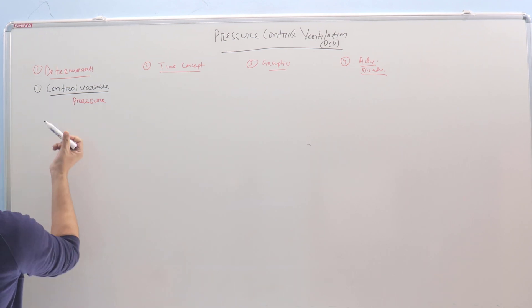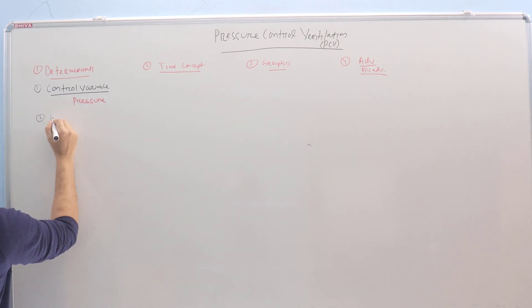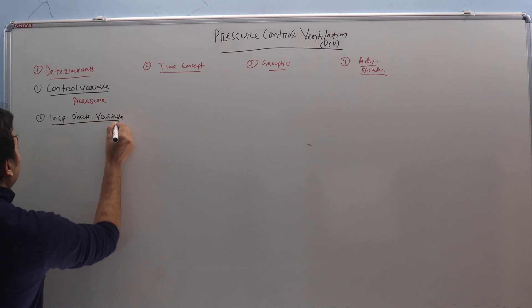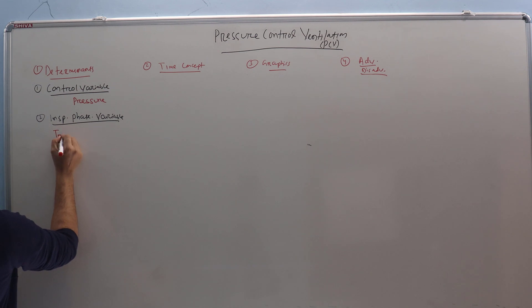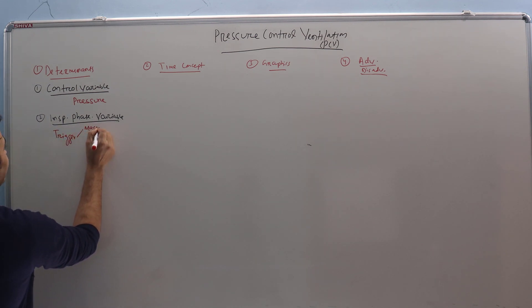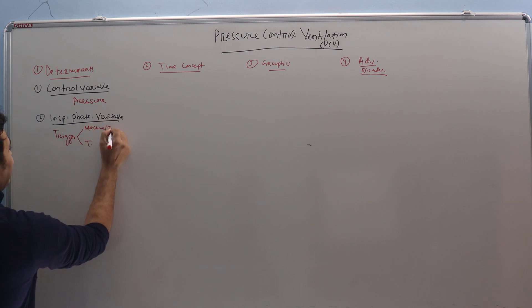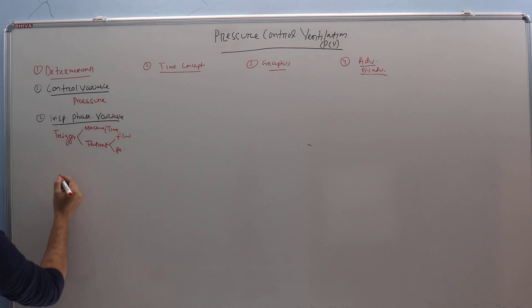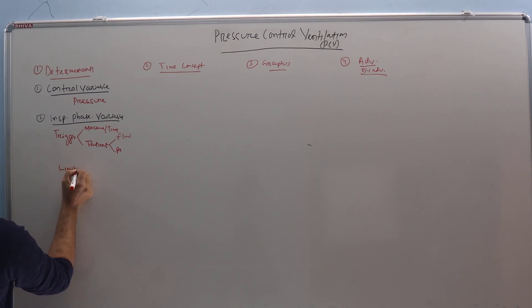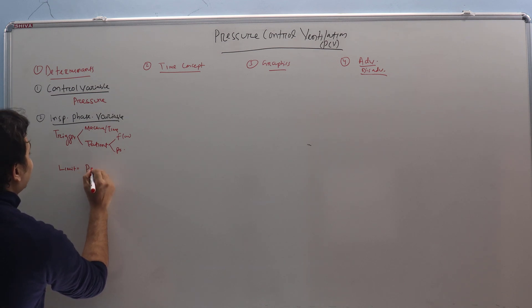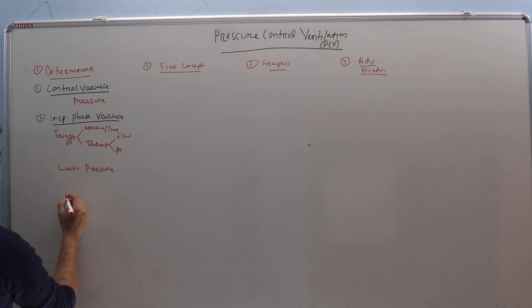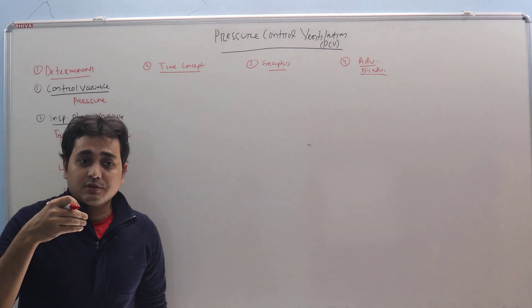The second heading will be Inspiratory Phase Variable and this will again be three types. First is Trigger — either machine, time, or patient, which can be flow trigger or pressure trigger. Second will be Limit — Pressure Control Ventilation will be pressure limited. And then Cycle — it will be time cycled, meaning we will set the Inspiratory Time and as soon as the time is over, the ventilator will cycle from Inspiration to Exhalation.